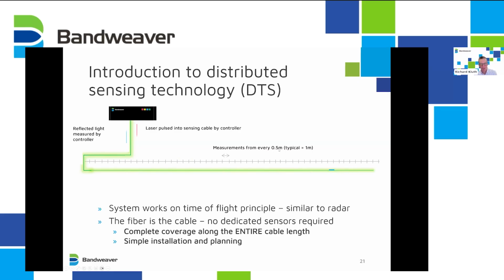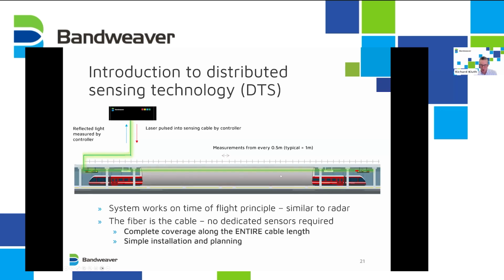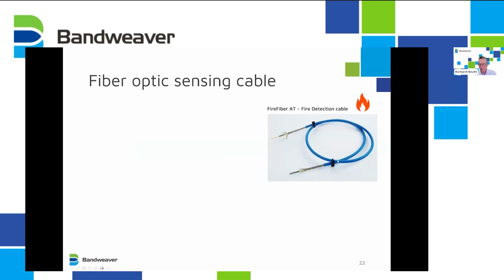There's no benefit to the additional information, and it's more effective from a data optimization and storage point of view to use 1 meter. And then if you run that in the installation, you get temperature at all points, and so you can detect the fire very accurately to where it starts. Just to be clear, the fiber is the cable. There's no dedicated sensors. You have complete coverage along the entire length, and it's very simple to install and much less planning, because you don't need to worry where each sensor is. You're measuring everywhere. This is our FireFiber AT fire detection cable.